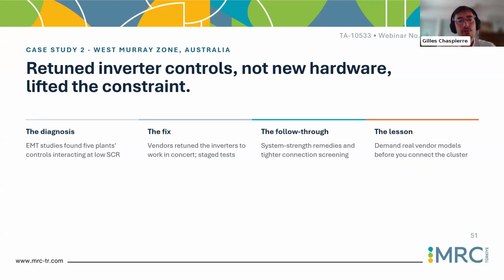So here the major difference is that it's not a blackout, it's not a cascading effect, it's just permanent oscillations that systematically appear when the system in the West Murray zone in Australia was losing a line after a short circuit. I think it's not really the short circuit that led to this oscillation, it's more losing this specific line. And the message here is that you lose a line, you increase impedance, you decrease voltage stiffness, meaning you have a higher voltage sensitivity.